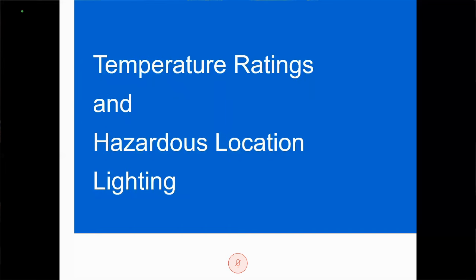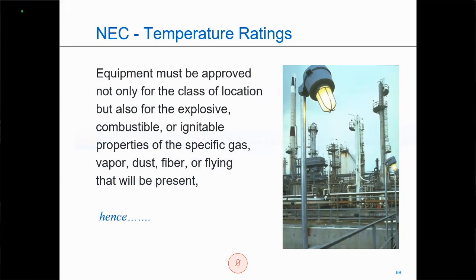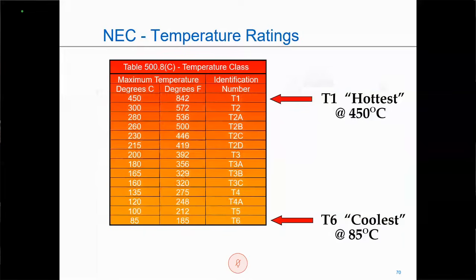Now, when it comes to temperature ratings and my hazardous location lighting, I'm not only going to be concerned with class, division, and group, I'm also concerned with temperature ratings. Now, T1 is my hottest, and T6 is my coolest. So if heptane has an auto ignition temperature of 204 degrees C, for that piece of equipment to operate safely in the area with heptane, I need to have a unit that is T3 rated. Because if I had a unit that was rated T2D, under worst case scenario, that piece of equipment can get up to 215 degrees C.